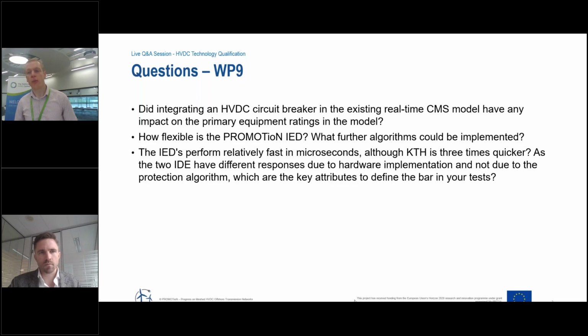Brent, I think that's a point to highlight, because KTH seems to average about 150 and yours is hitting about 500, microseconds, but the limit is about 2 milliseconds or something like that, so it's still well within the margin of operation you need. When you see the two side by side, I know which one I'd rather be installing in a substation, because I didn't need to turn yours off to cool down every now and again. So yeah, that dual redundant architecture and the realness is part of it there. But it's by far and away quick enough.